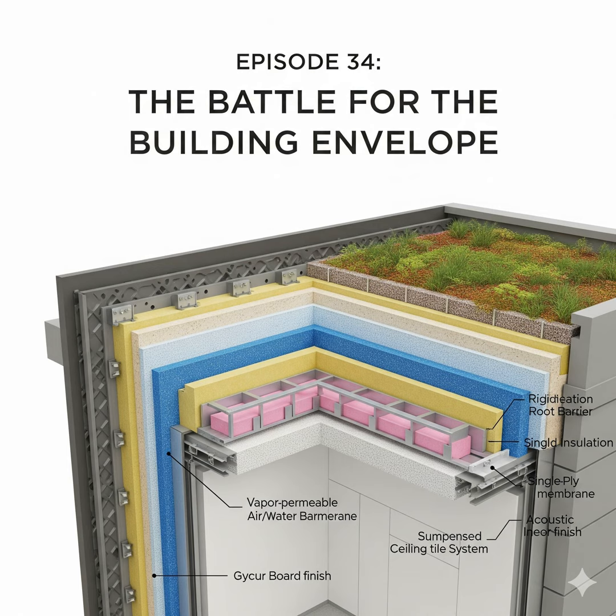So the vapor retarder stops the vapor before it hits that cold surface. Ideally, yes. Typically, in cold climates, you put the vapor retarder on the warm side of the insulation, usually just behind the drywall. It stops warm, moist indoor air from getting into the cold wall cavity. Okay, makes sense for cold climates, but why is it bad elsewhere?